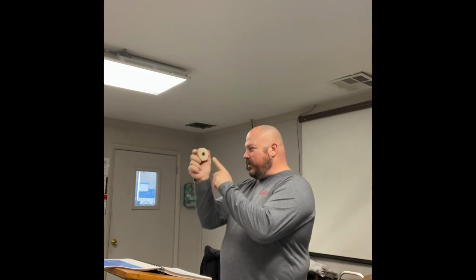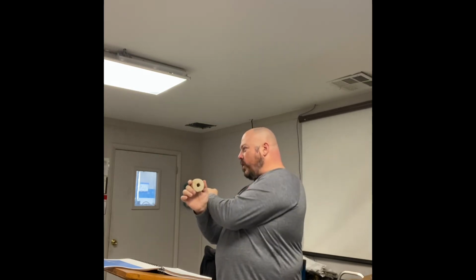Metering device. This now becomes a metering device, because you have a restriction here. The restriction is now between here and the compressor. When this becomes a restriction and there's flow on the other side, we know it's a low flow. We know that there's less pressure on this side of it, because this is the blockage. This becomes a metering device, even though it's still in that small line. It's still metering through here. It's flashing through this line, and it's not liquid by the time it gets to the real metering device.